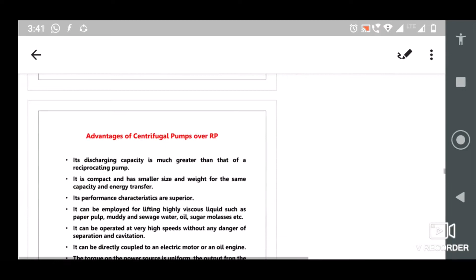And next we move on to the advantages of your centrifugal pumps over your reciprocating pumps. There are a lot of advantages. With the centrifugal pump, compared to the reciprocating pump, the discharge capacity is much greater, and it is compact and small in size and weight. Also, the major important one is that performance is obviously greater than reciprocating pumps. It can be employed for lifting highly viscous liquids, or muddy liquids or sewage or other kinds, and it is operated at very high speeds without any danger of separation, and you don't have the major problem of cavitation. It can be directly coupled to the electric motor, and the torque or power source is very uniform.